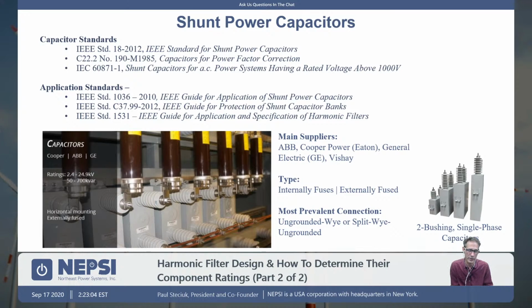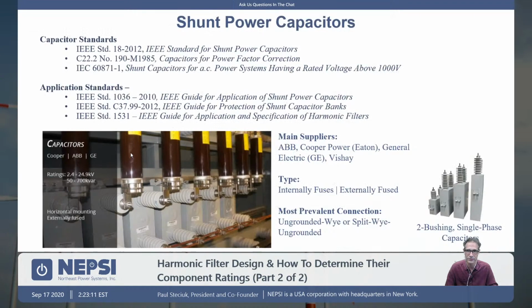Capacitors can be either internally or externally fused. Here I show a capacitor that's externally fused. By and large, NEPSI is utilizing externally fused capacitors. We do not use internally fused capacitors. One is not necessarily any better than the other. Our preference, and especially the preference in North America, is to use externally fused capacitors. We like them, and one of the key reasons is that the capacitor itself is simpler. There are not as many connections on the inside of that capacitor when the fuses are put external to the capacitor. The other thing is when a capacitor fails, it blows the fuse. It operates this fuse here. We can see that the fuse has operated. An indicator pops up. We know that the fuse has operated. So it's a preference thing, but I also believe that there's not a significant difference between these two types of capacitors.